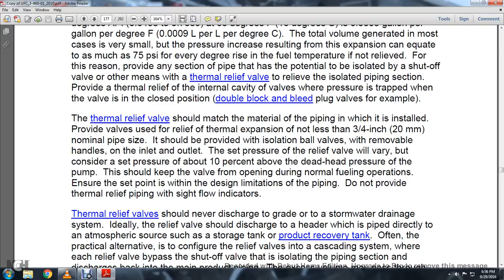Do not provide thermal relief piping when the sight flow indicators are present. Thermal relief valves should never be discharged to a storm water drain. Ideally, the relief valve should discharge to a header which is piped directly to an atmospheric source, such as the storage tank or the product recovery tank. Often the alternative is to configure the relief valves in a cascading system, where each relief valve bypasses the shut-off valve that is isolating the piping section, discharging back into the main product piping. The excess volume may pass through two or more relief valves, finally making its way back to the atmospheric source.